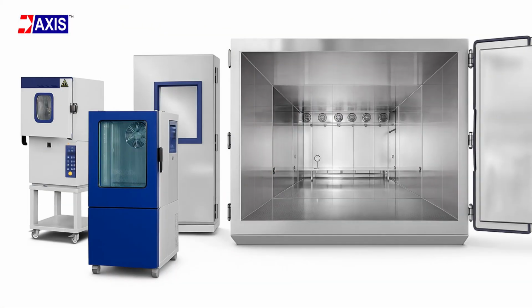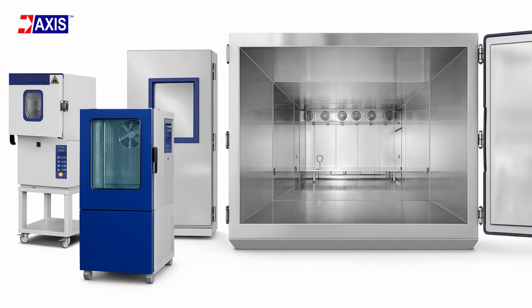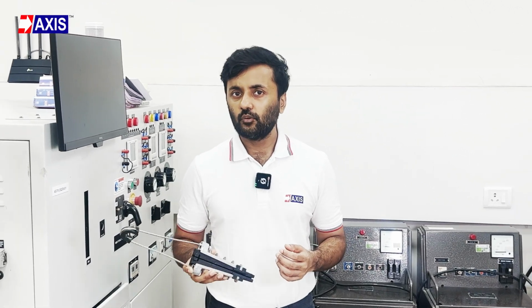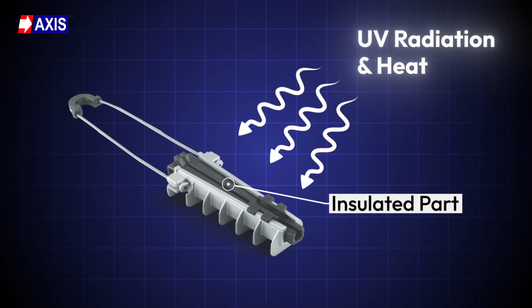The goal of this test is to check if the clamp can withstand long-term exposure to temperature, moisture, and UV radiation without degrading. So how do you conduct this test? Install the clamp on the largest cross-section of insulated neutral messenger. Place the clamp inside a climatic chamber under accelerated environmental cycles that reproduce natural weathering. In the chamber, the sample goes through 6 weekly cycles at 70 degrees Celsius. The clamp is mounted such that the side of the cable entry faces the light sources. This setup ensures the insulated part is exposed to full UV radiation along with heat.